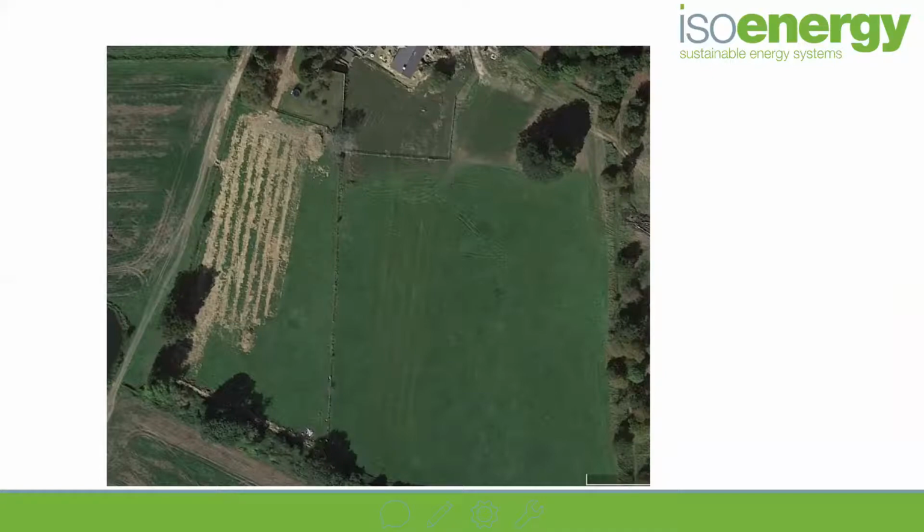We've got a question from Robert Archer. Is it better to have the pipes buried deeper than a metre, more heat deeper down? No, there's no benefit to going any deeper than a metre. Below 1.2 or 1.5 metres, you have to shutter the trenches, which leads to exorbitant costs, and there's next to no thermal benefit. We're not actually looking for geothermal heat.